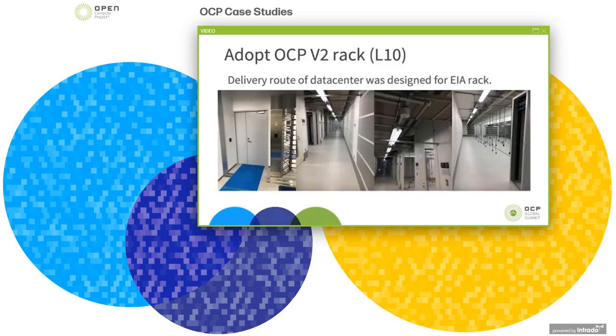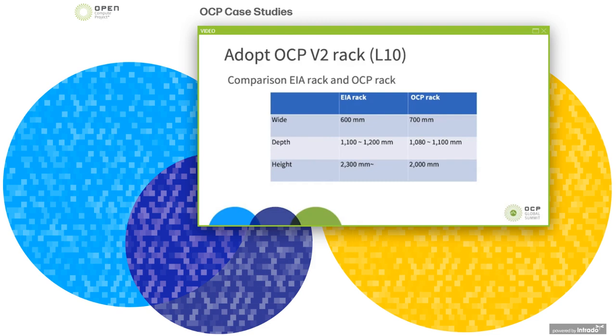This is the delivery route of the data center where we wanted to adopt version 2 OCP racks first. The data center was designed for EIA racks, which needed to be assembled inside the IT space. But OCP racks arrive full load, so the access route from the goods-in area to the IT space only considered the size of the IT gear, not including the rack. Let me show the size of the OCP rack and the EIA rack.